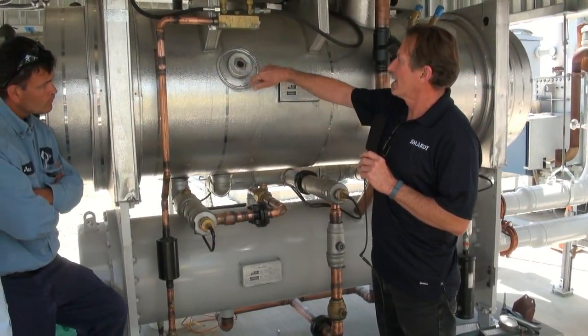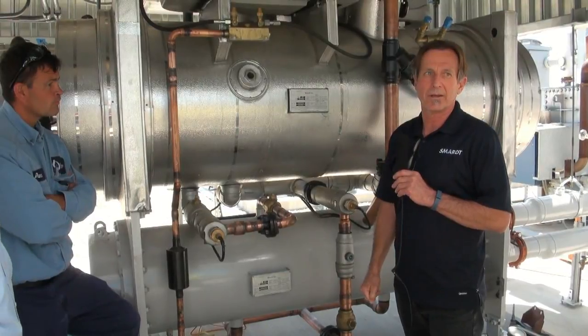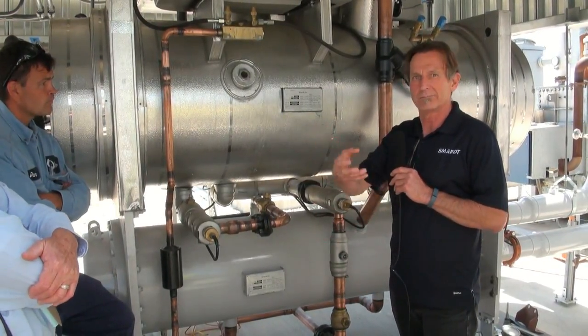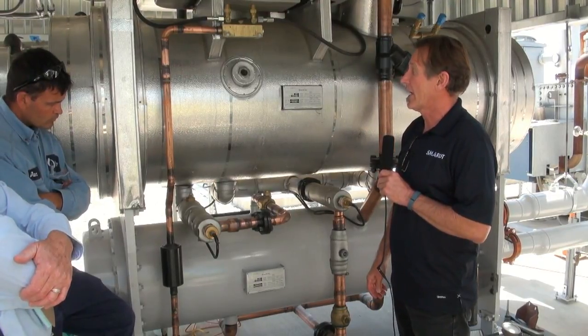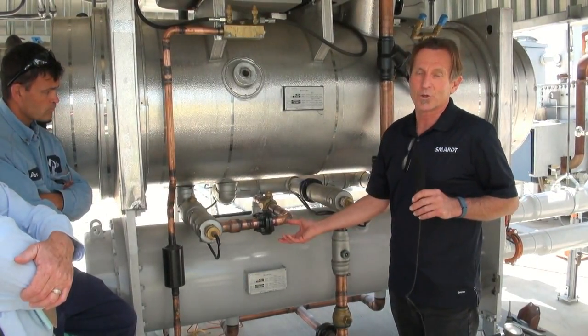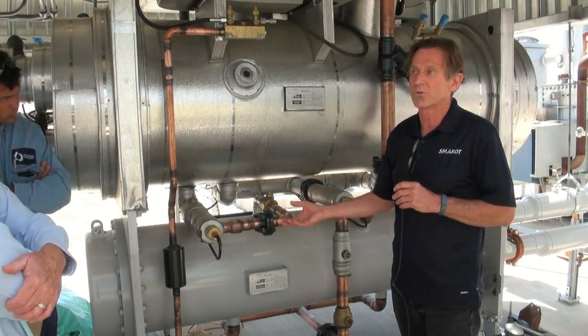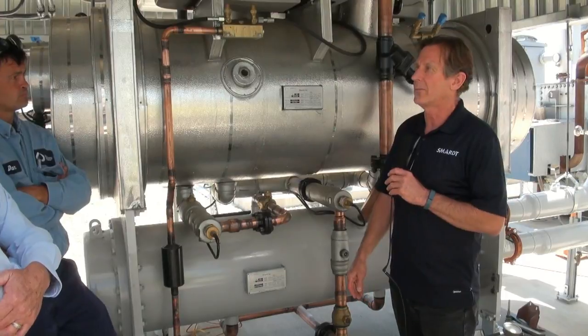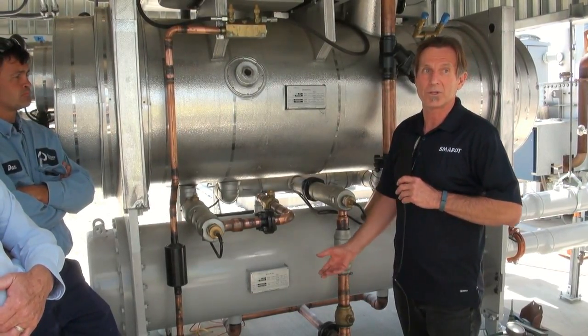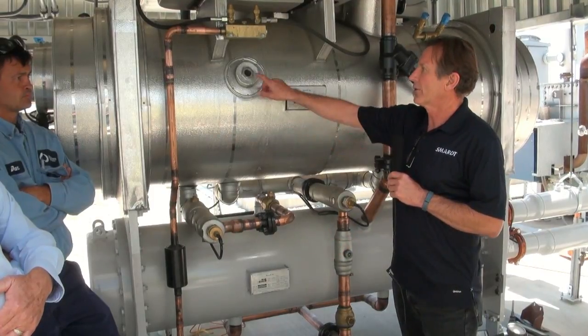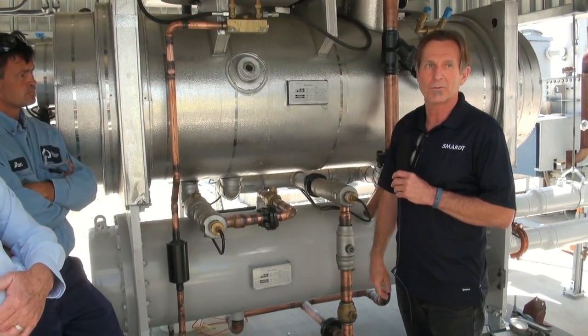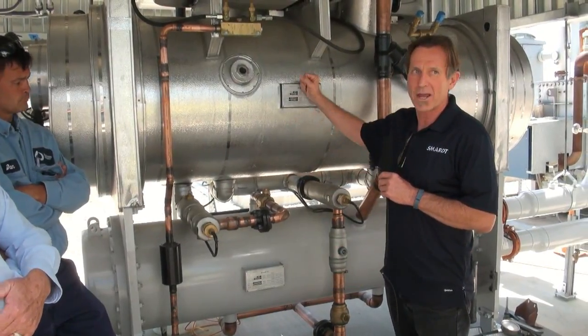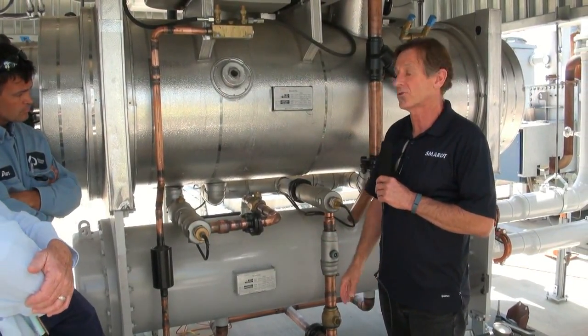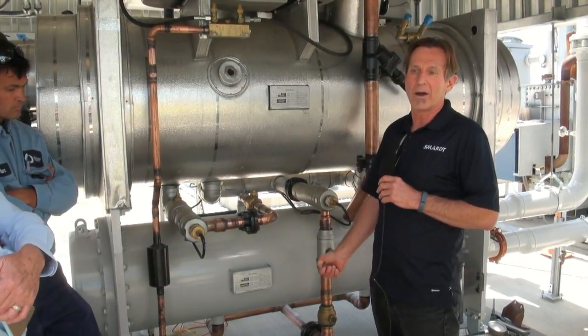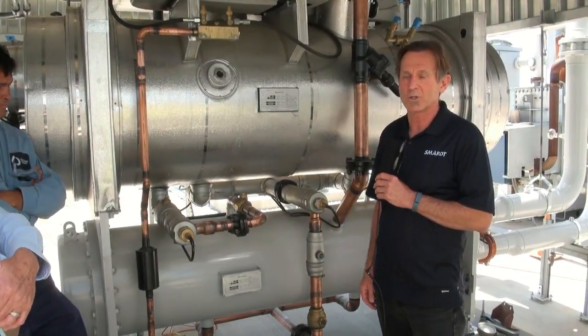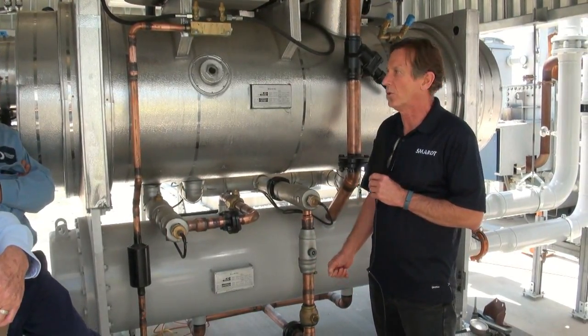Yeah, that gives you a peek inside the evaporator, and you can see the tubes, and that's about it. You might see a little refrigerant coming above the tubes if you take a peek in there. It's useful at times. If you're having motor cooling issues, you see you're not maintaining a solid column of liquid for your motor cooling, and you go, well, geez, why don't I have refrigerant in my condenser? And you look through the sight glass and you see it's full of refrigerant. Well, you know where your refrigerant went. It's all stacked in the evaporator, not being held in the condenser. So at that point, I'd investigate why my valves aren't keeping the refrigerant where it's supposed to be. So yeah, that's an indicator. It's a good tool. It can be useful at times.